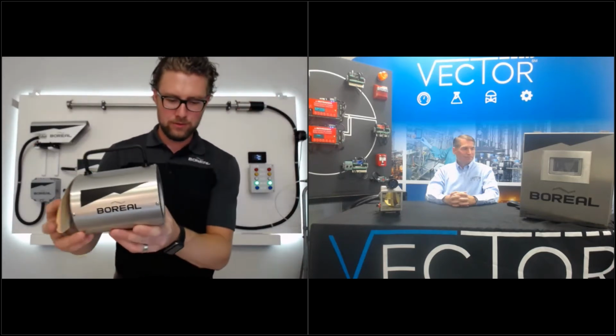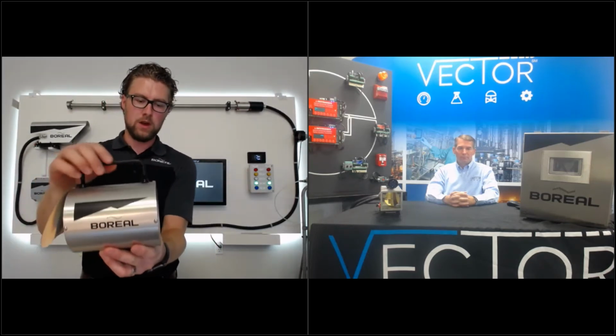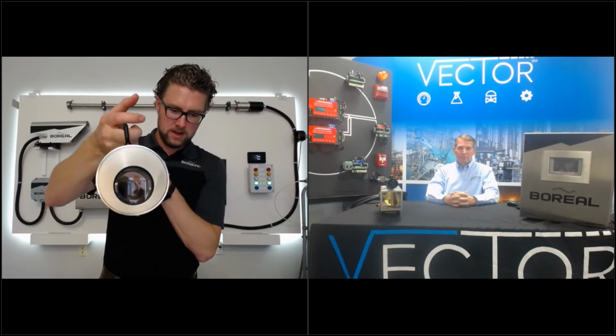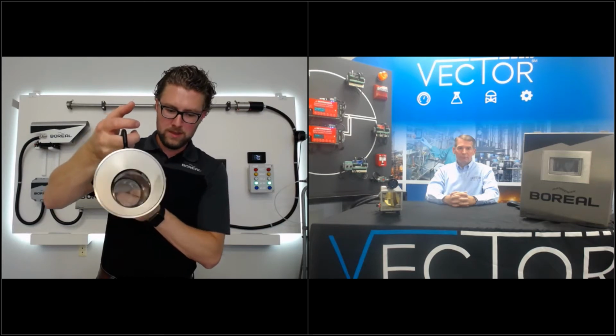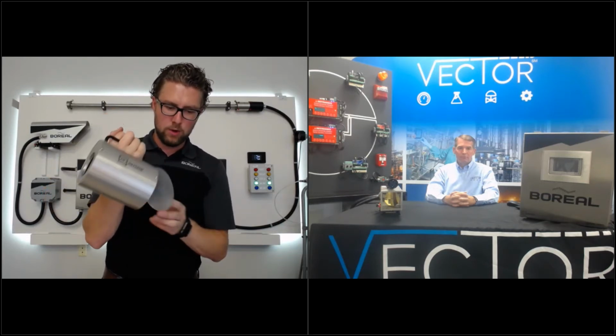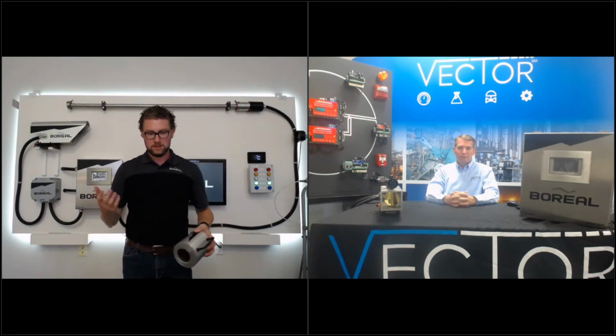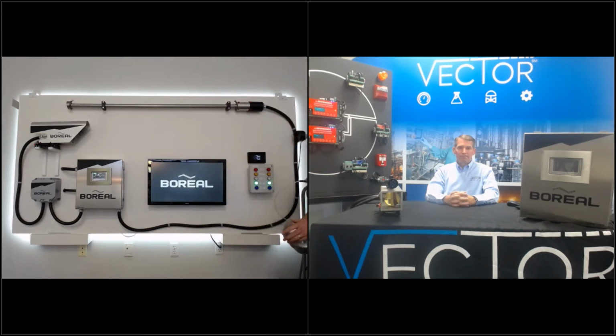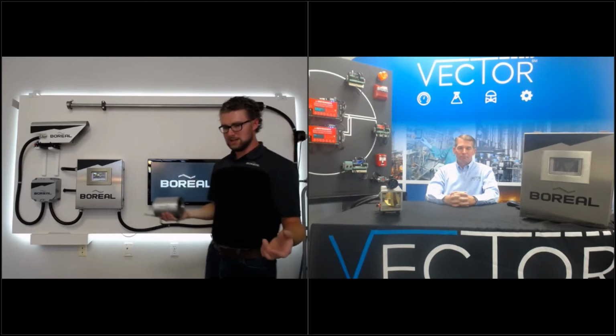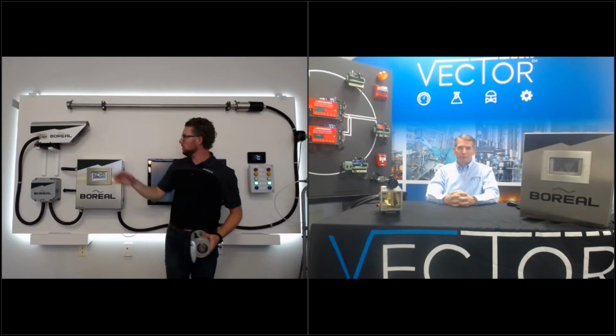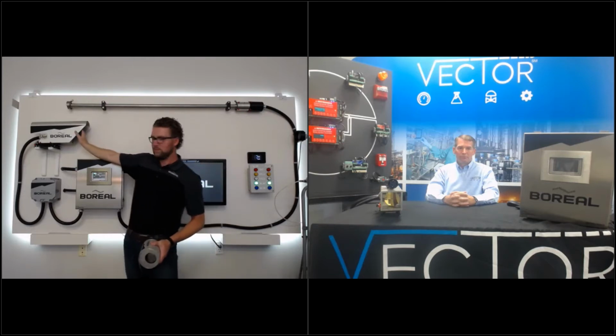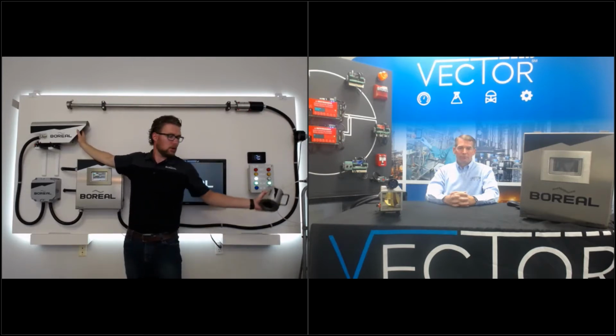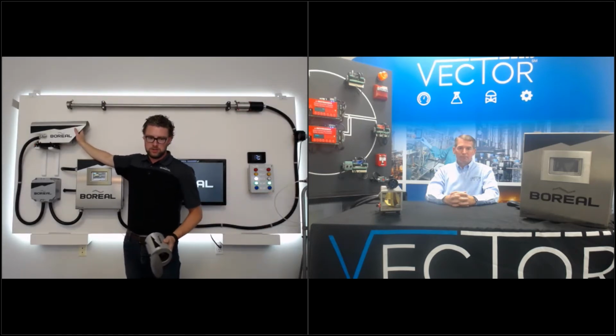So I'm going to step to the camera, allow it to focus for a second. What we have here is a reference cell. Inside of here, there is a tube of glass. In this case, it's filled with methane. Inside of here, we have a little retro flap if required, or we can move it out of the way. Your preventative maintenance routine is simply walking up to your active measurement path, placing this within the beam, exercising your alarm relays, and you have fully functioned, fully end-to-end tested the full functionality of this system and this equipment. It can be placed anywhere within the active measurement path. I'll show you once again, if the system is on and working, our low lights, our beam block status indication shows that there's been a change, an inhibition to the system. So that validates that functionality.